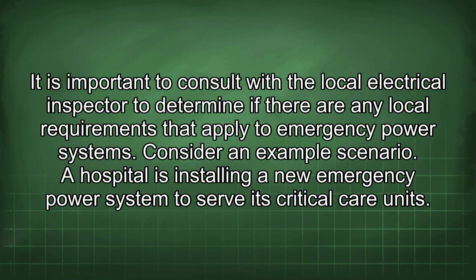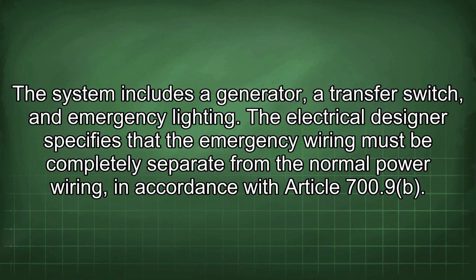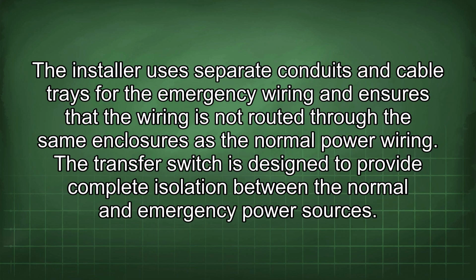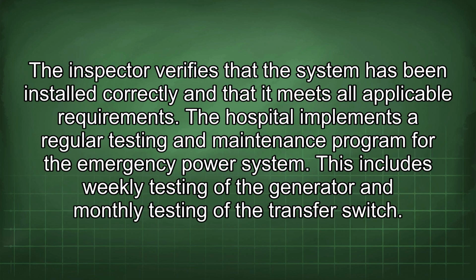A hospital is installing a new emergency power system to serve its critical care units. The system includes a generator, a transfer switch, and emergency lighting. The electrical designer specifies that the emergency wiring must be completely separate from the normal power wiring, in accordance with Article 700.9 B. The installer uses separate conduits and cable trays for the emergency wiring and ensures that the wiring is not routed through the same enclosures as the normal power wiring. The transfer switch is designed to provide complete isolation between the normal and emergency power sources. The inspector verifies that the system has been installed correctly and that it meets all applicable requirements.